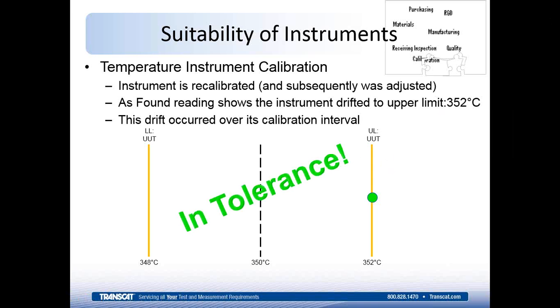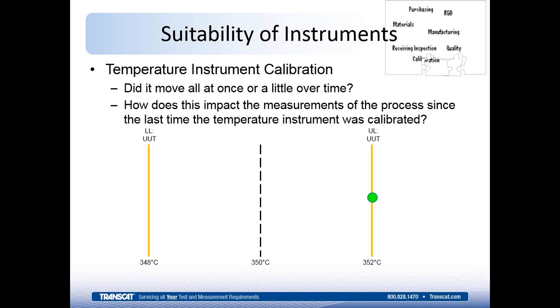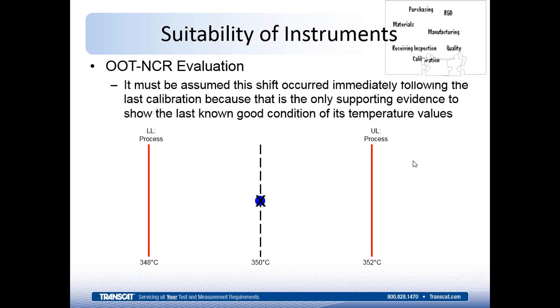So the instrument is found in tolerance because it's not gone outside that limit. And the question is, now I've got to evaluate, even though that's not out of tolerance, did that measurement move all at once due to some abrupt change in the use of the temperature device, or did it do a little bit over time over that cal interval? And how does that impact the measurements of the process since the last time the temperature device was calibrated? So you have to assume that the instrument shift occurred immediately following the last calibration, even though likely it didn't, because you don't have any other supporting evidence to show when it actually had shifted. And because you don't know when it shifted, you have to assume everything is in question. All right, so again, it's not found out of tolerance, but there's a drift there that's pretty significant, and you need to see if that had an impact.